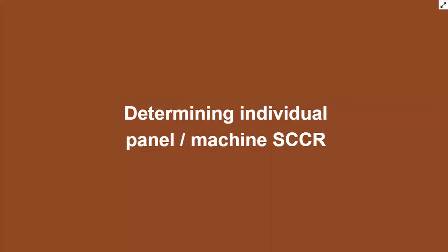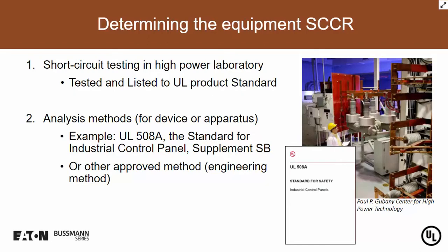How are we going to determine the SCCR? Let's start with what we can do. Well, number one, we could take it to a testing laboratory and have our machine tested and have it blow up to find out exactly what the SCCR would be. And then you would have to rebuild the machine. And most likely we wouldn't do that. The second option would be to use the UL 508A analysis method that UL 508A Supplement SB can do for you. Or you can do an approved engineering method that would do the same thing and determine the SCCR for that machine or the industrial control panel itself.